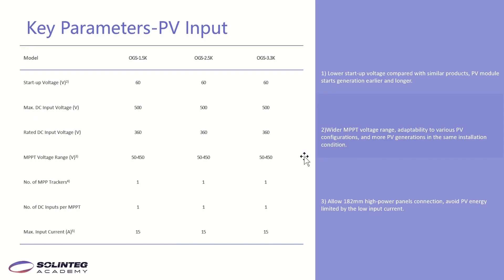Now let's look at the key parameters. This page shows the PV input parameters. The start voltage is very low — only 60V — so compared to similar products, it starts earlier. The MPPT voltage range is 50V to 450V, which is a wide range that can adapt to various PV configurations for more power generation under the same installation conditions. The maximum inverter input current is 15A, enabling connection with large-format panels such as 182mm modules.